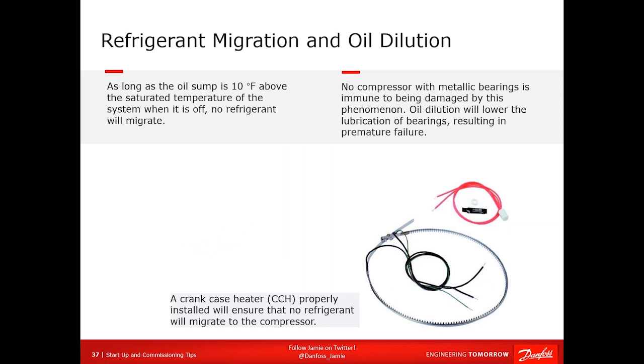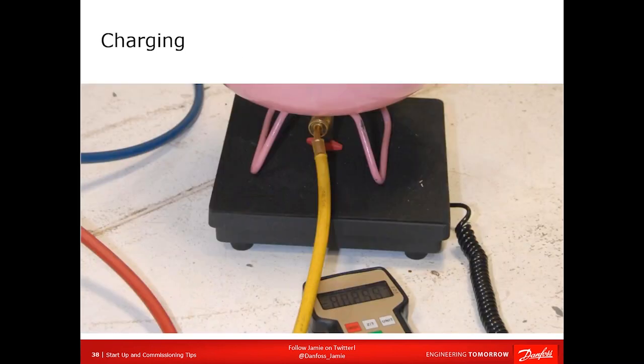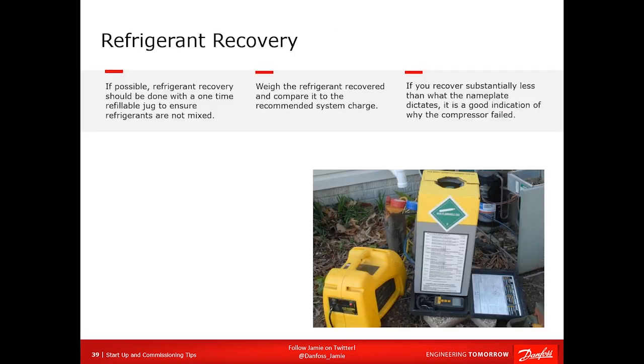How do you stop that? Crankcase heater. As long as your oil is 10 or 15 degrees above the rest of the system, you are not going to have refrigerant migrate into the oil. So if it sounds like it's grinding on startup, that is probably refrigerant in your oil. Fix it by having a crankcase heater. Remember, 12 hours minimum, 24 hours preferred before you start the system.